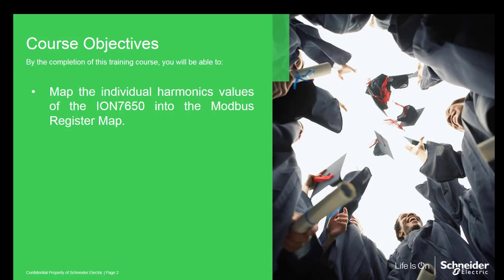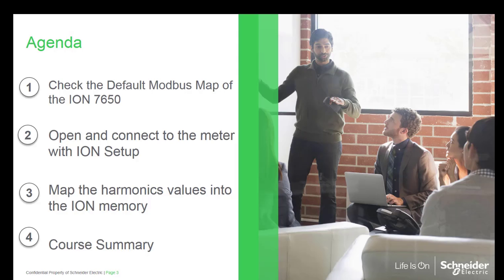The course objective will be to map the individual harmonic values of the ION7650 into the Modbus register map. To do that, we will follow this agenda. First of all, we will check the default Modbus map of the ION7650. Then, we will open and connect to the meter with ION Setup. Next, we will map the harmonic values into the ION memory, and finally we will make the course summary.